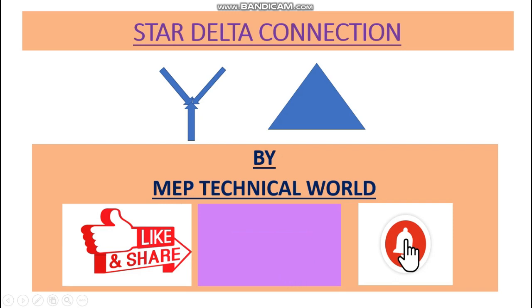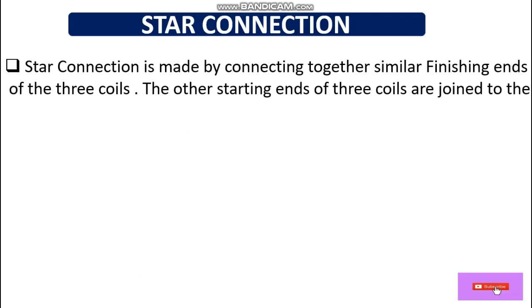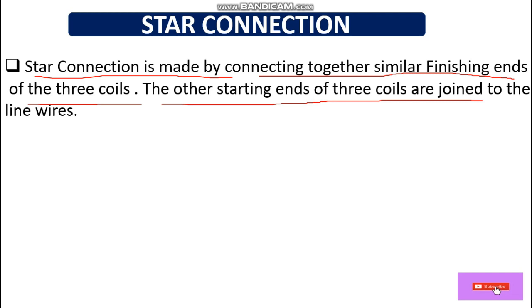So basically, what is a star connection? A star connection is made by connecting together the similar finishing ends of three coils; the other starting ends of the three coils are joined to the line wire. In a three-phase system, whether it's a motor or alternator, we always have three coils.